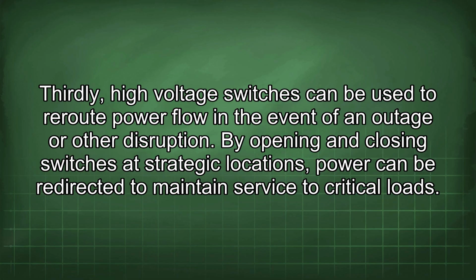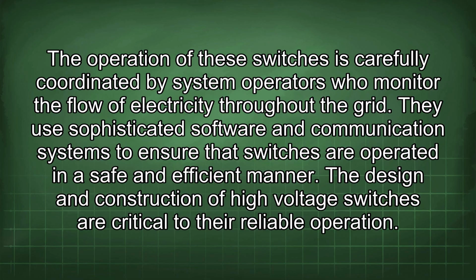Thirdly, high voltage switches can be used to reroute power flow in the event of an outage or other disruption. By opening and closing switches at strategic locations, power can be redirected to maintain service to critical loads. The operation of these switches is carefully coordinated by system operators who monitor the flow of electricity throughout the grid. They use sophisticated software and communication systems to ensure that switches are operated in a safe and efficient manner.